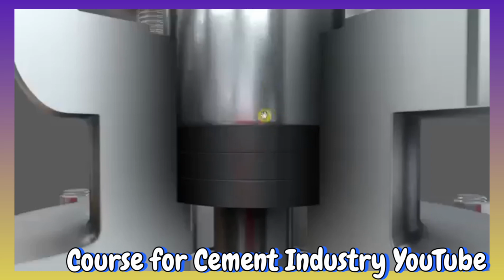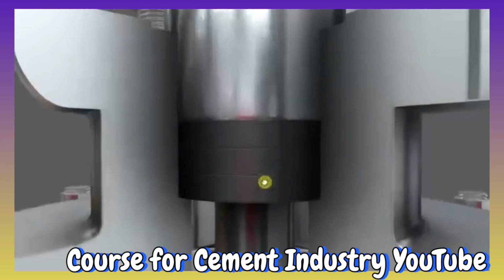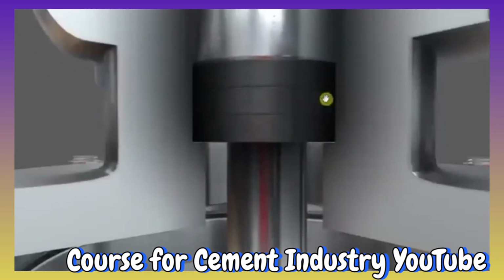And as this is compressed, the packing is going to be squeezed against the stem, this piece here, and the bonnet, which is this piece here. And that's what gives us our seal, and that's what prevents the valve from leaking.